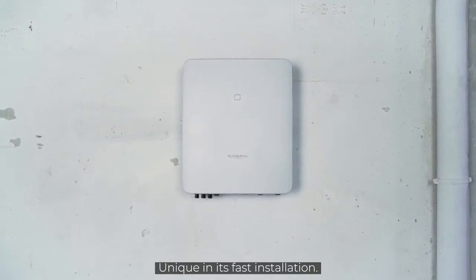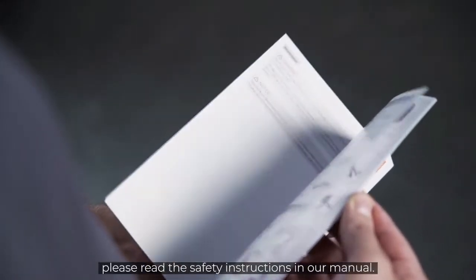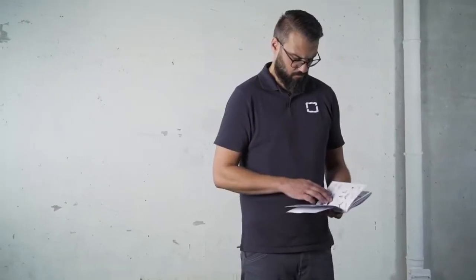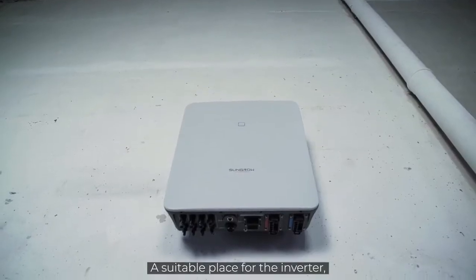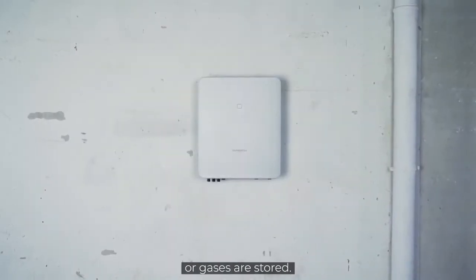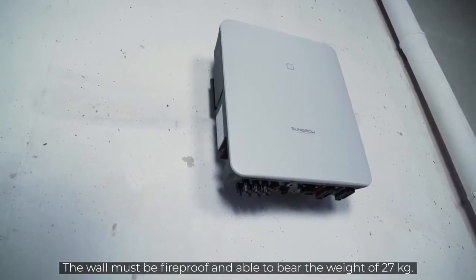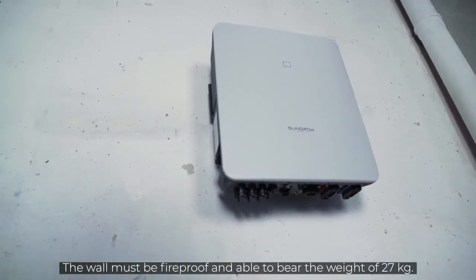Unique in its fast installation. Before starting the installation, please read the safety instructions in our manual. You need a suitable place for the inverter. This means it should be a room where no flammable materials or gases are stored. The wall must be fireproof and able to bear the weight of 27 kg.